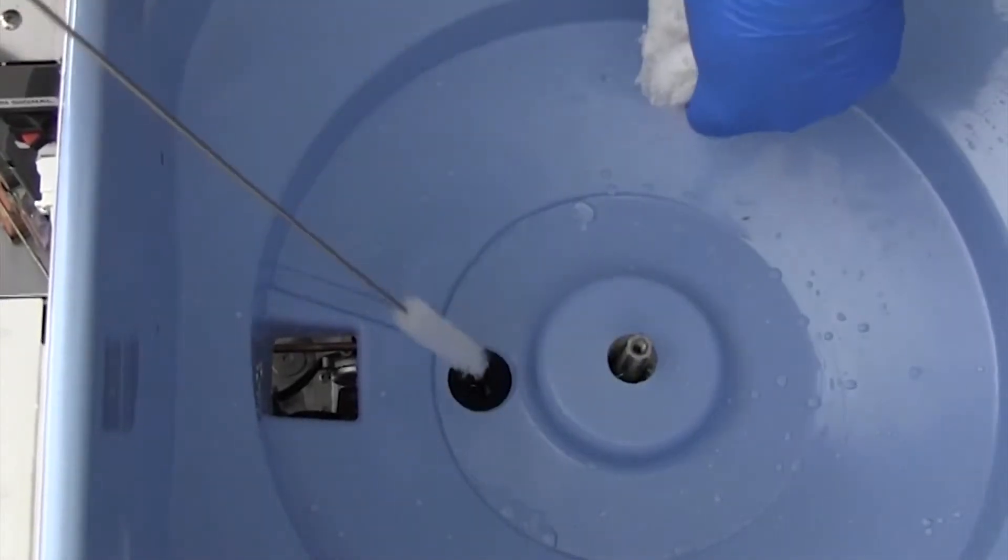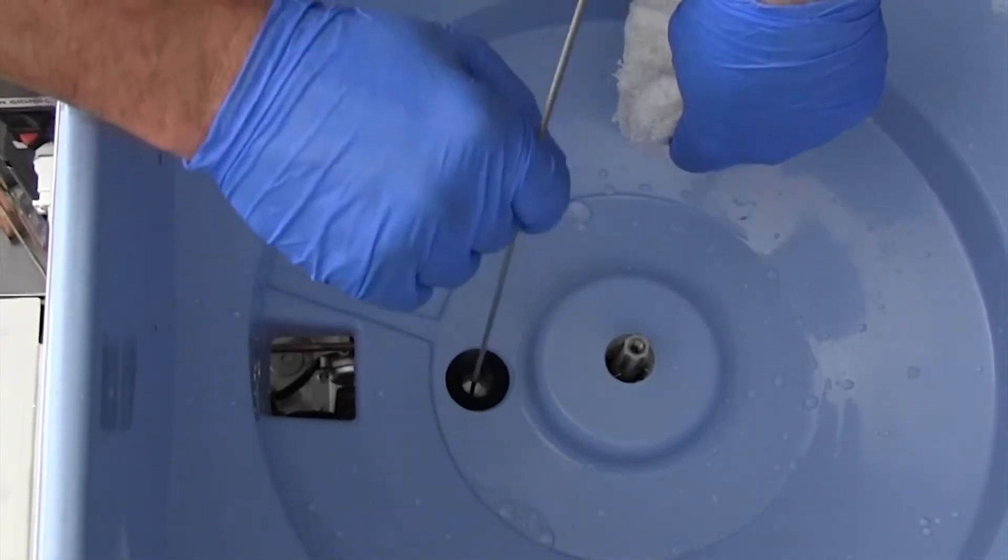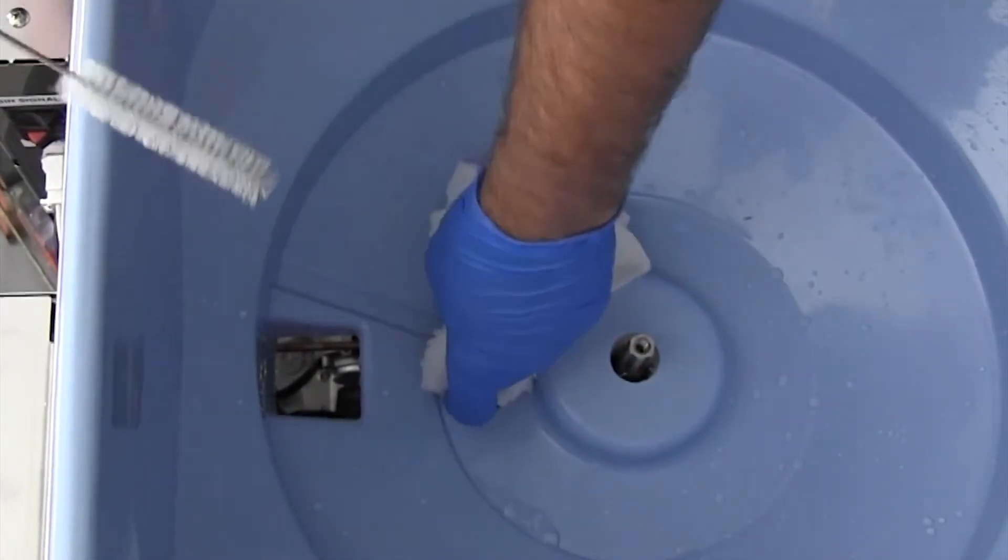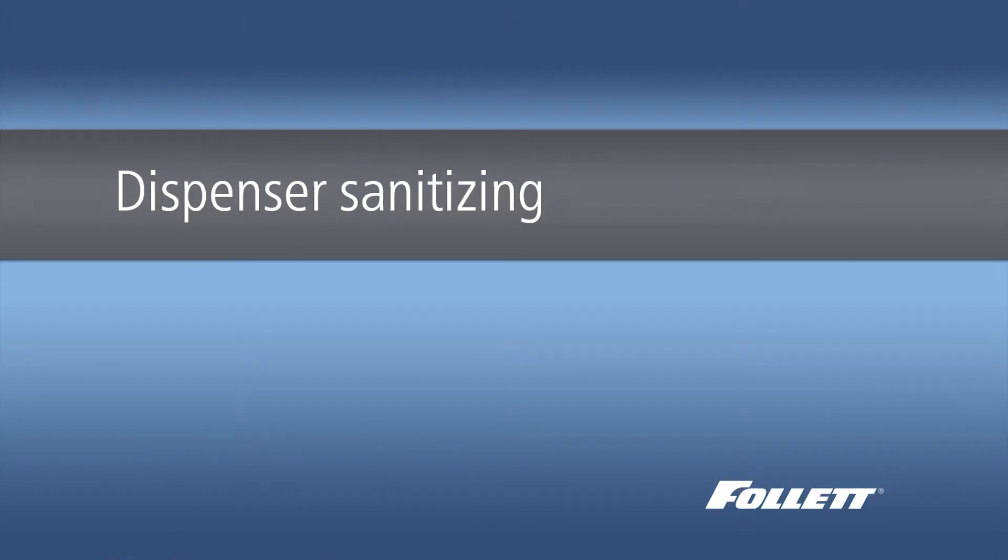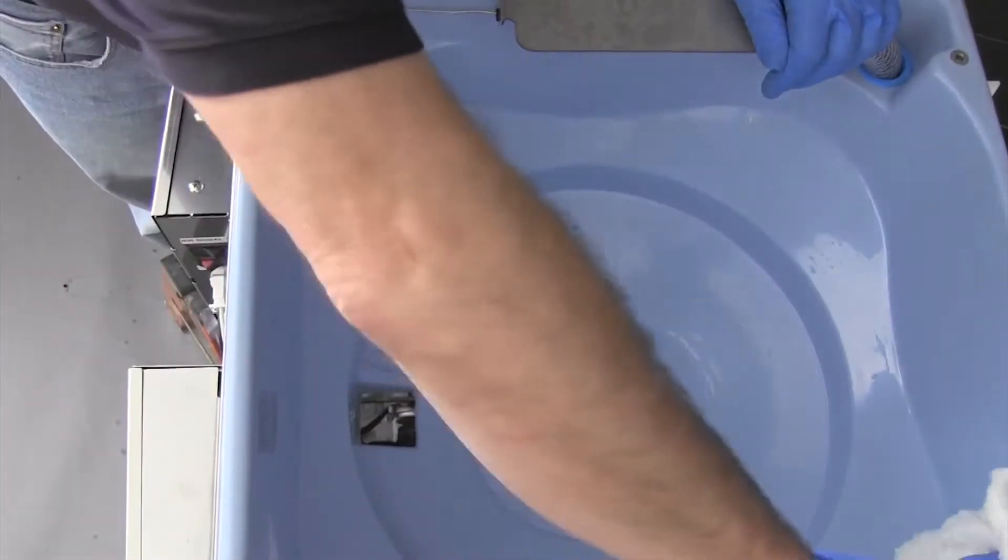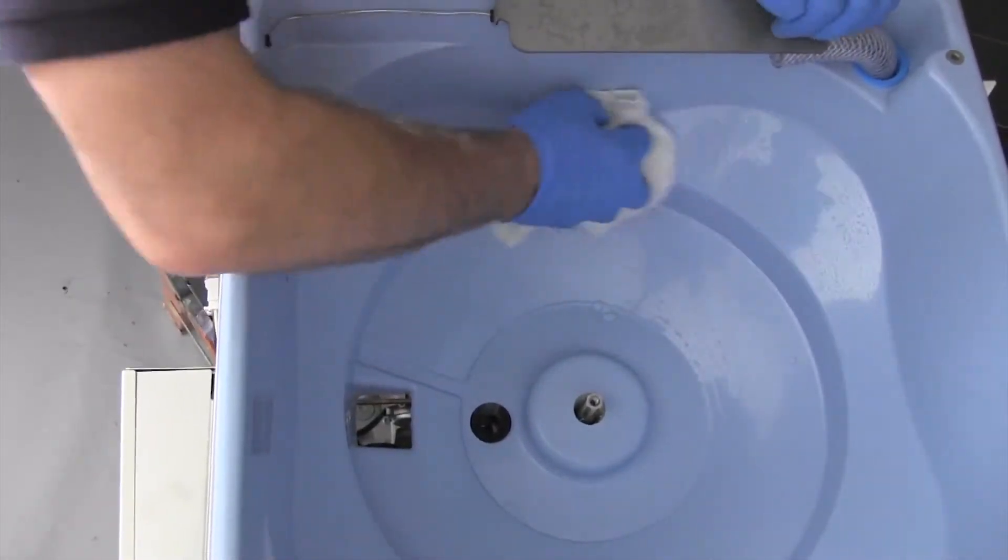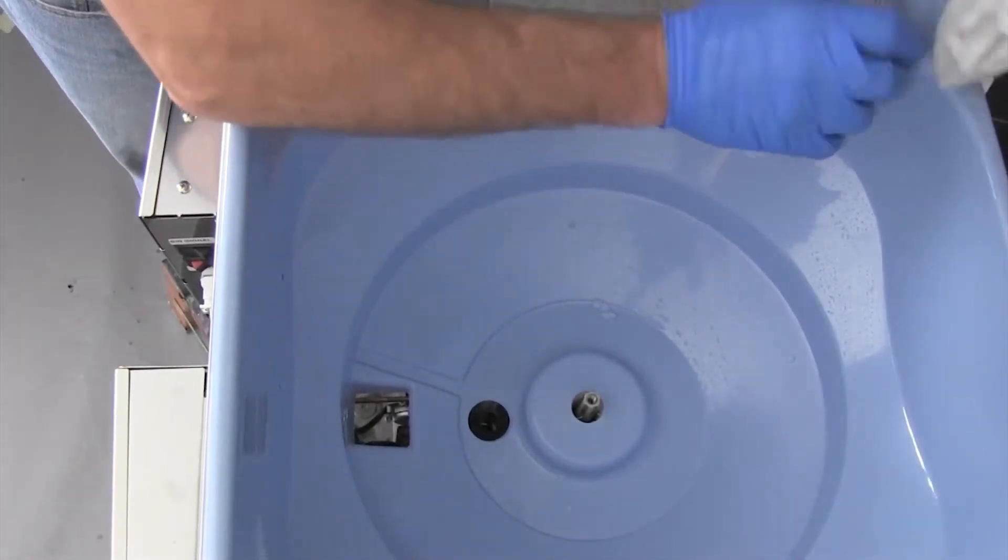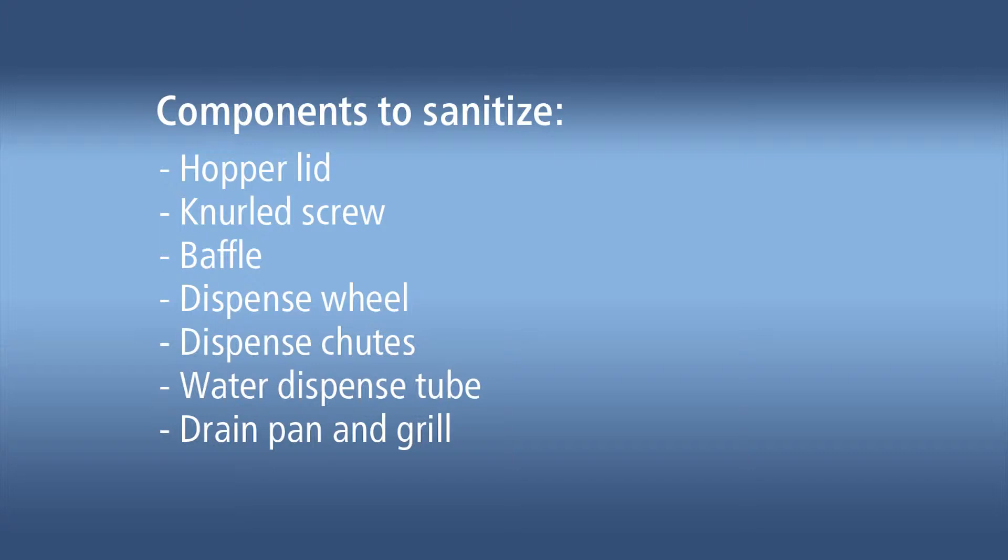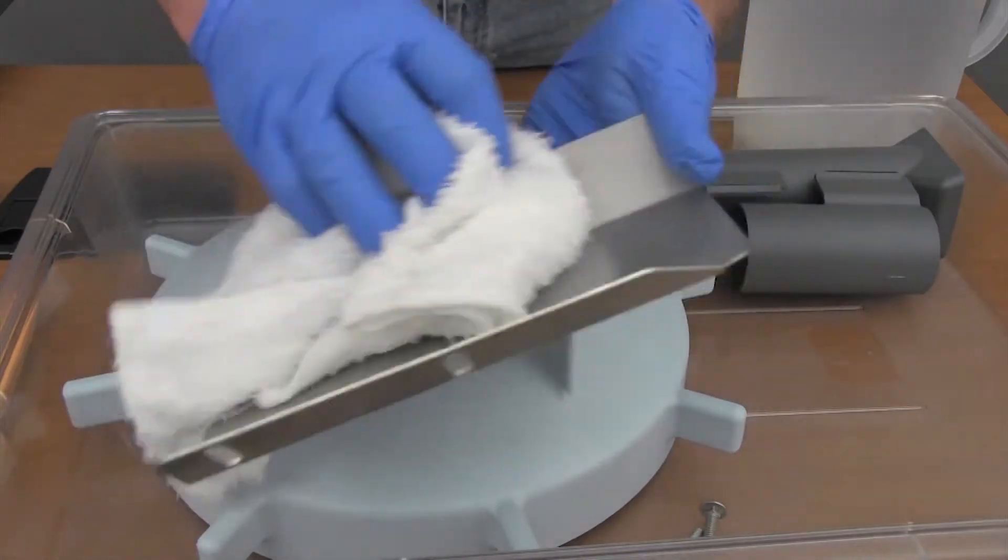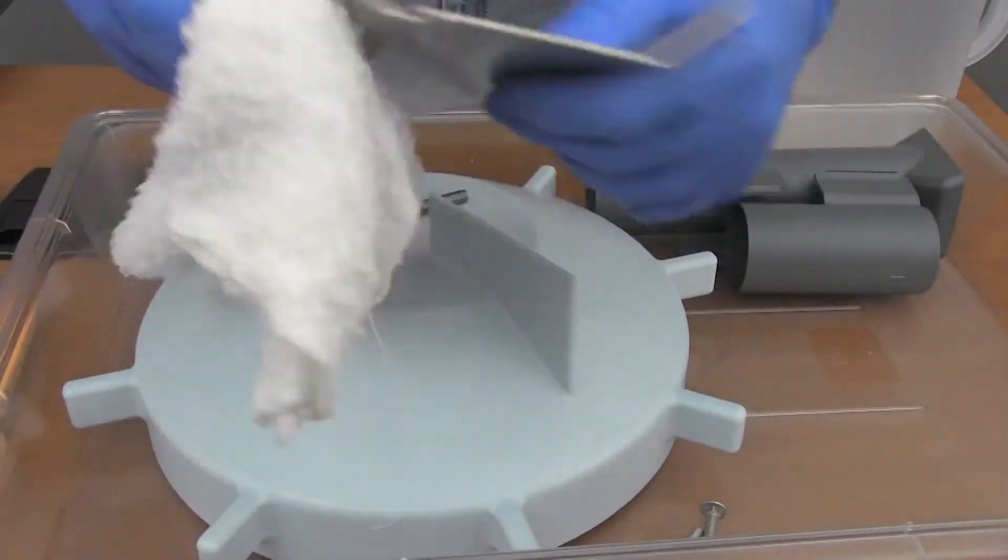Sanitize the hopper drain line by dipping a clean 3-quarter inch bottle brush into the sanitizing solution and running it through the drain fitting into the drain line. You can use the 15-minute cycle time to sanitize the dispenser. Use a soft cloth that won't damage surfaces. Do not use abrasive products such as scouring pads. Dip, wring out, and wipe down each of the dispenser components with the sanitizing solution. Reinstall each of the dispenser components without rinsing. This treatment keeps surfaces sanitary during reassembly.